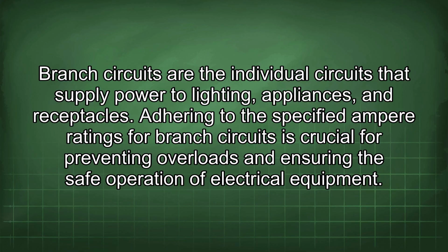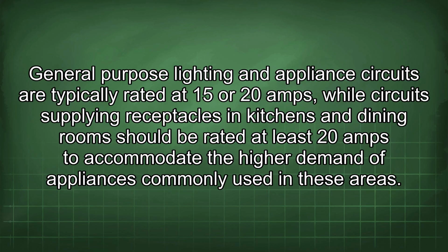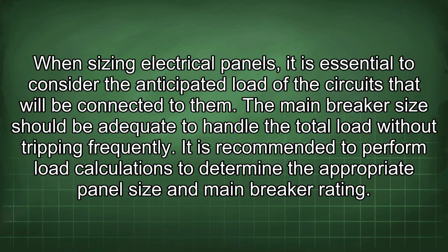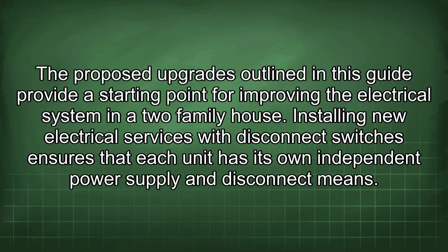electrical equipment. General purpose lighting and appliance circuits are typically rated at 15 or 20 amps, while circuits supplying receptacles in kitchens and dining rooms should be rated at least 20 amps to accommodate the higher demand of appliances commonly used in these areas. When sizing electrical panels, it is essential to consider the anticipated load of the circuits that will be connected to them. The main breaker size should be adequate to handle the total load without tripping frequently. It is recommended to perform load calculations to determine the appropriate panel size and main breaker rating. The proposed upgrades outlined in this guide provide a starting point for improving the electrical system in a two-family house.